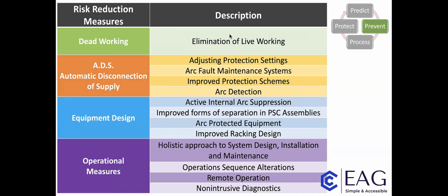So prevent must be the focus of attention when managing the risk of harm from arc flash. This table categorises those risk reduction measures into dead working, which must be the principal prevention measure. The second one, in orange, is automatic disconnection of supply, ADS, which is the detection of dangerous arcing current, then the automatic disconnection of supply. The third category is equipment design. And finally, operational measures.